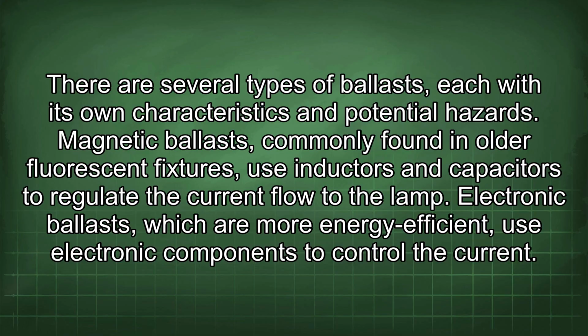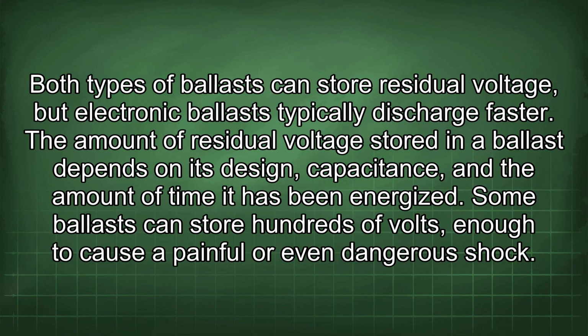Magnetic ballasts, commonly found in older fluorescent fixtures, use inductors and capacitors to regulate the current flow to the lamp. Electronic ballasts, which are more energy efficient, use electronic components to control the current. Both types of ballasts can store residual voltage, but electronic ballasts typically discharge faster. The amount of residual voltage stored in a ballast depends on its design, capacitance, and the amount of time it has been energized. Some ballasts can store hundreds of volts, enough to cause a painful or even dangerous shock.